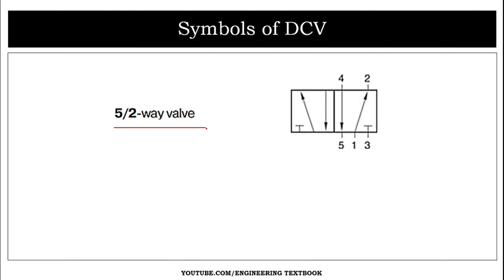The five by two valve has two positions and five ports: one, two, three, four, and five. Port one is the pressure port; ports two and four are work ports; ports three and five are exhaust ports. Oil from port one transfers to port two towards the cylinder, and oil returns from the cylinder through port four to port five — the exhaust port — while port three is closed.